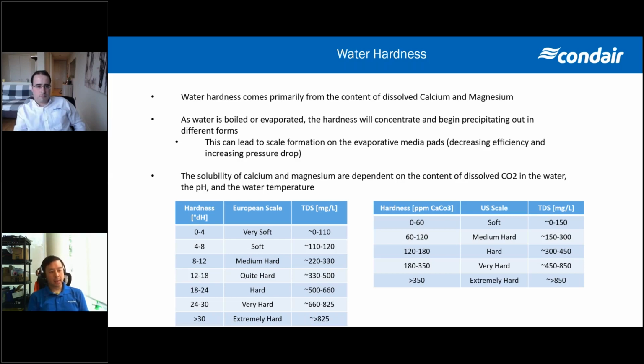So the solubility of the calcium and the magnesium are dependent on a few different factors: dissolved CO2 in the water, as well as pH and the water temperature. Depending on where you are, we've got a European scale for hardness. Here in North America, we typically look at hardness as ppm of calcium carbonate.